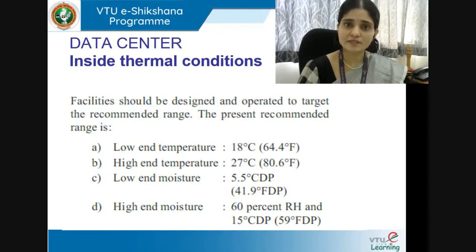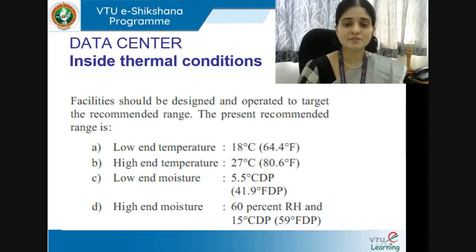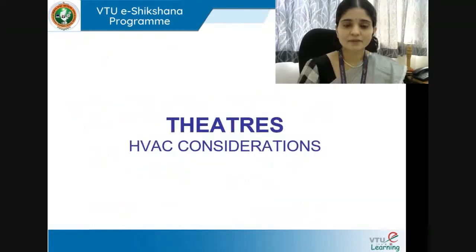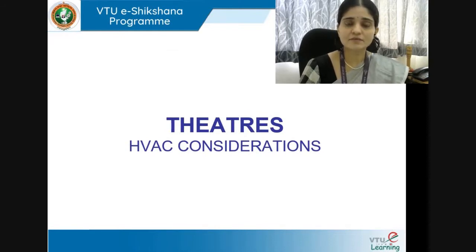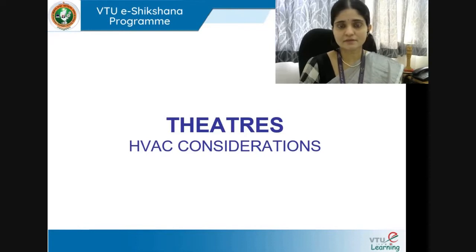NBC offers standards and the recommended range for temperature and moisture. The indoor thermal conditions advised in the NBC are: low end 18°C, high end 27°C, and moisture at 60% RH. That is a brief of the intent by which we have to design our server room HVAC systems — the main objective being sensible heat gain and addressing cooling loads accordingly.